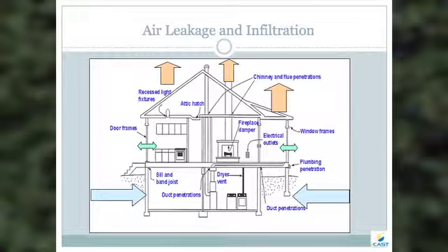So you're going to have air trying to force its way out above you at the ceiling line, and that's going to create a vacuuming effect down below in your lower levels or towards your basement. Wind effect is very similar to the stack effect, except it's created by wind, and it tends to go in a horizontal manner. So you have wind blowing against the side of a house, and if you see in this picture the neutral pressure plane on this side, as you blow against, say, the right-hand side of the house in this slide, that neutral pressure plane begins to tilt, okay?